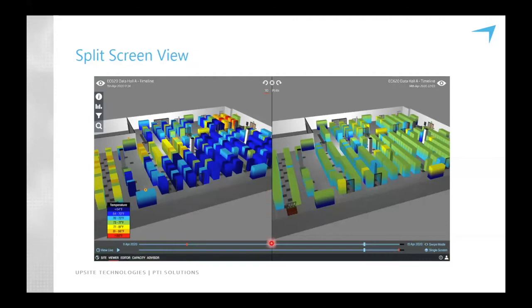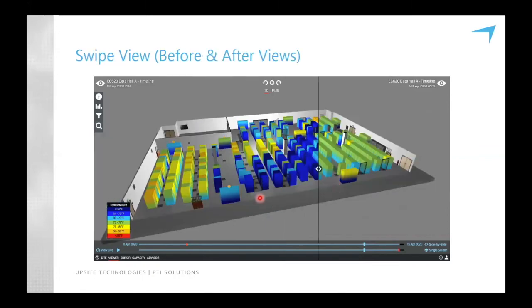Here's a before and after comparison on the timeline. You see here across the bottom of the screen that the timeline starts from deployment of the solution and runs to the current moment. And any two points in time can be compared either side by side like this or in a split screen view. And one of the things I want to point out is that here on the left is the before conditions, and you'll see an area of the room that's quite cold. These cabinets have very low intake temperatures and some warmer intake temperatures and even some quite high intake temperatures over in this corner of the room. Whereas in the after conditions, everything is more green and blue, a little bit of yellow, indicating that intake temperatures are up higher and more even, closer to that ASHRAE recommended limit of 80 degrees Fahrenheit. So much more optimized condition.